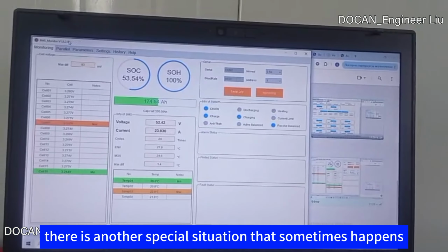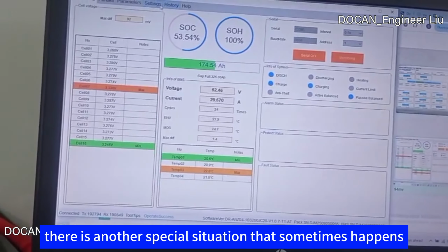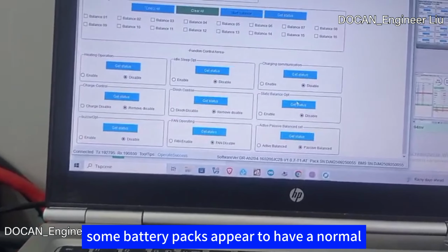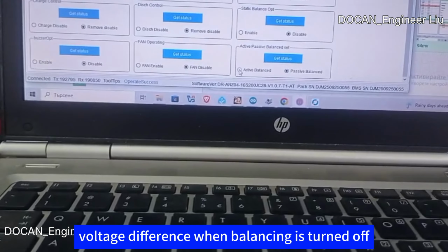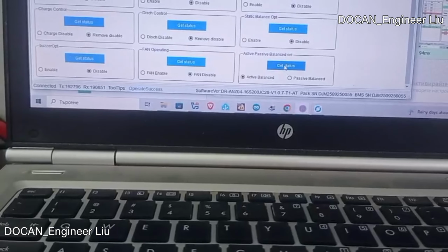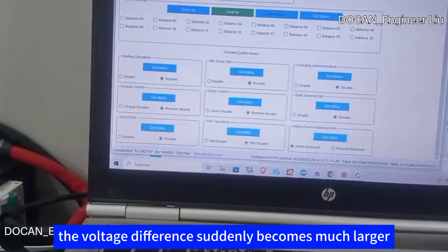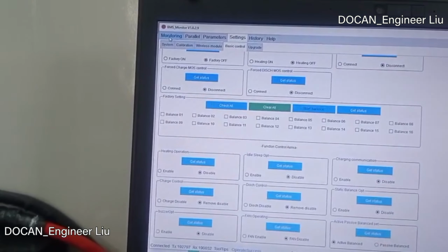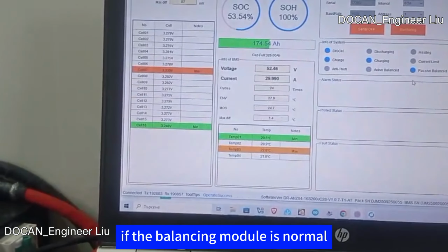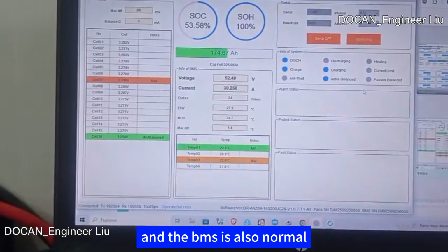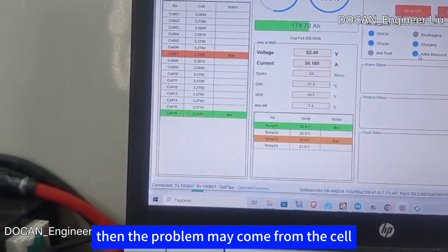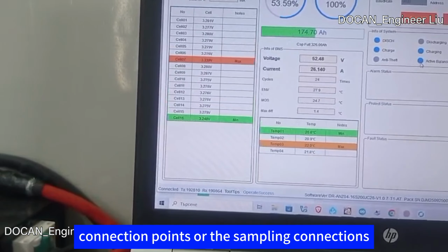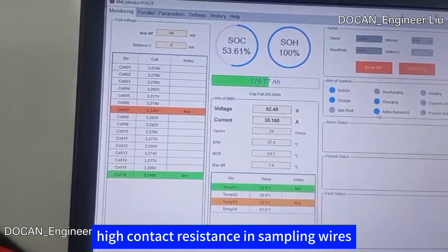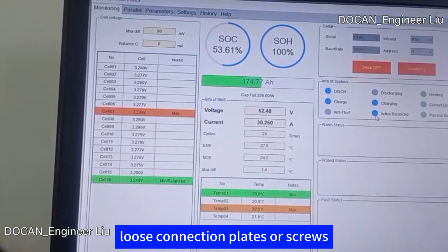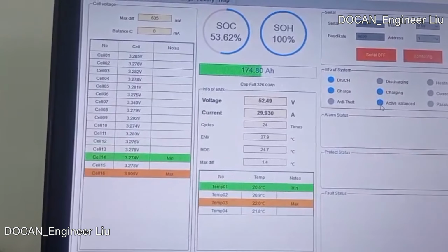Special situation. There is another special situation that sometimes happens. Some battery packs appear to have a normal voltage difference when balancing is turned off, but once balancing starts, the voltage difference suddenly becomes much larger. If the balancing module is normal and the BMS is also normal, then the problem may come from the cell connection points or the sampling connections. For example, high contact resistance in sampling wires, loose connection plates, or screws that are not tightened properly.